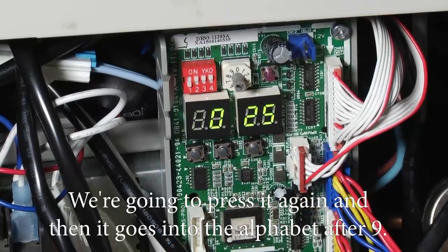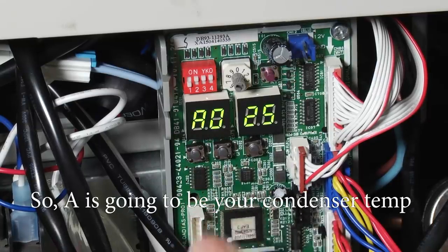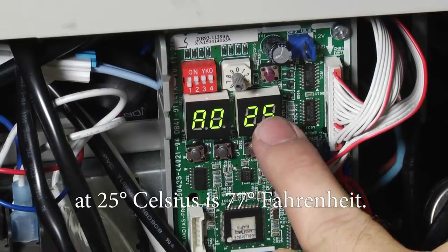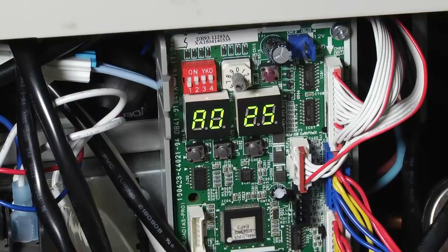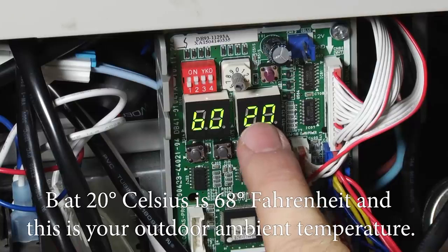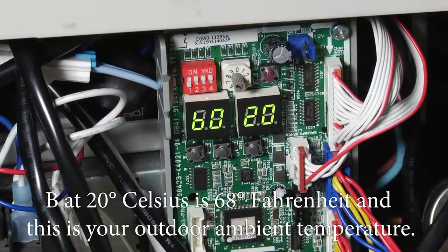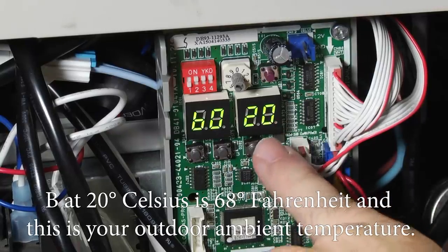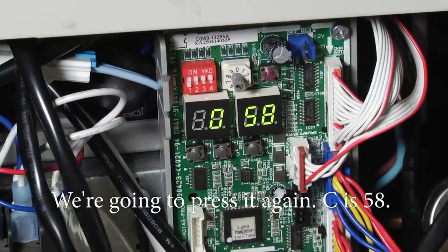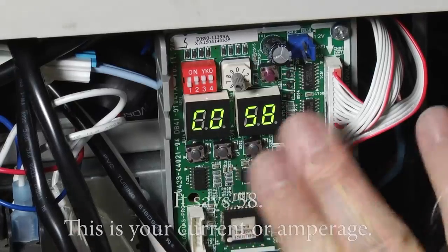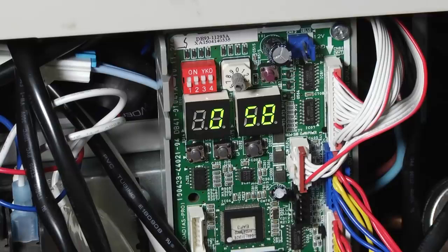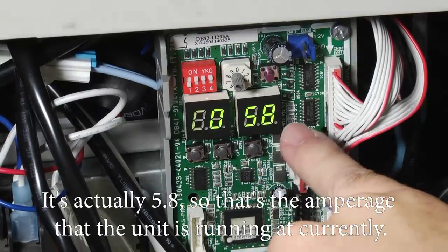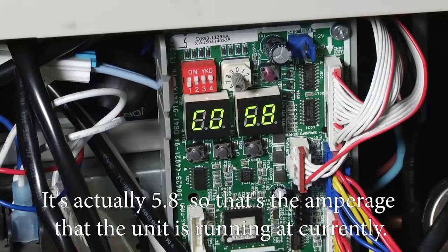We're going to press it again, and then it goes into the alphabet after 9. So A is going to be your condenser temp at 25 degrees Celsius, which is 77 degrees Fahrenheit. We're going to press it again. B at 20 degrees Celsius is 68 degrees Fahrenheit, and this is your outdoor ambient temperature. We're going to press it again. C says 58, but this is your amperage. It's actually 5.8, so that's the amperage the unit is running at currently.